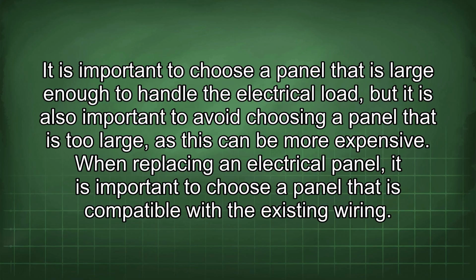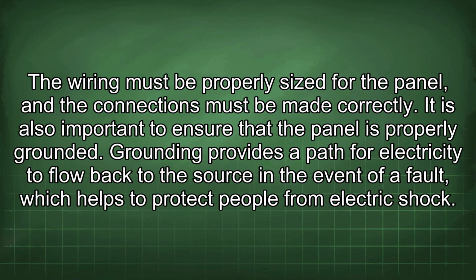When replacing an electrical panel, it is important to choose a panel that is compatible with the existing wiring. The wiring must be properly sized for the panel and the connections must be made correctly. It is also important to ensure that the panel is properly grounded. Grounding provides a path for electricity to flow back to the source in the event of a fault, which helps to protect people from electric shock.